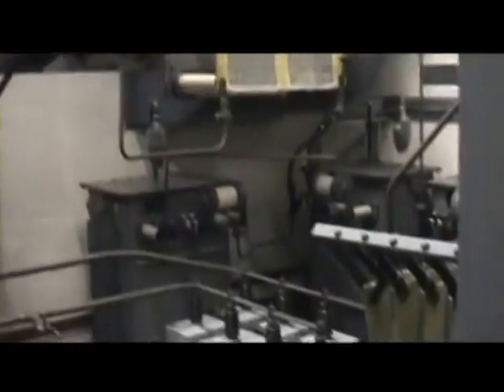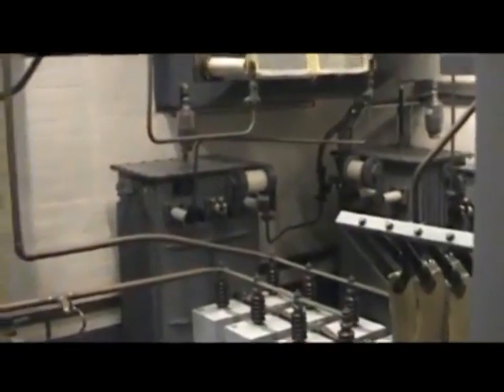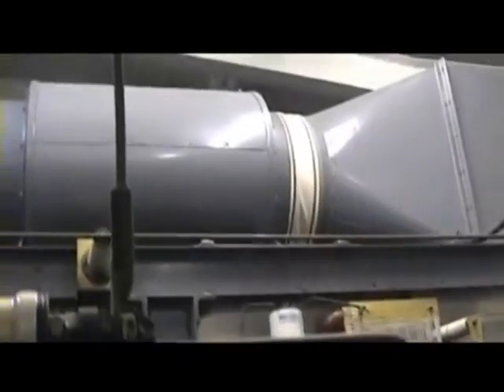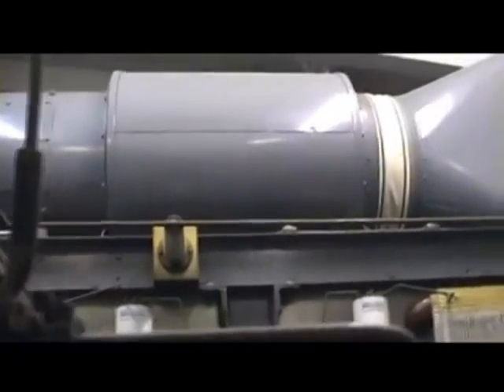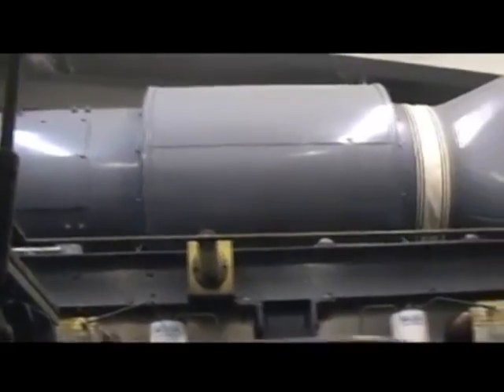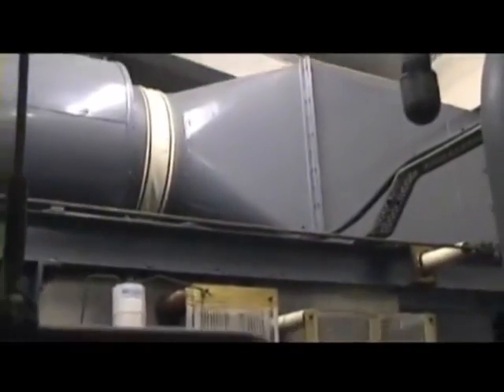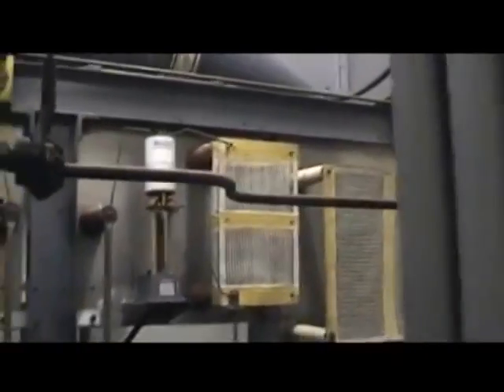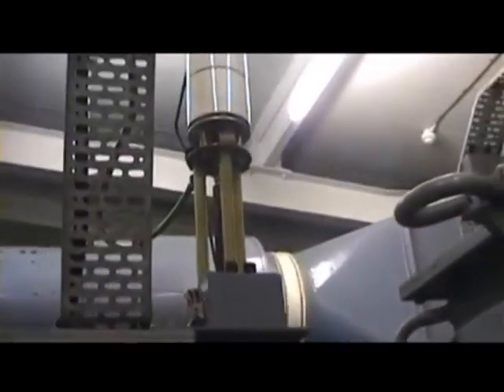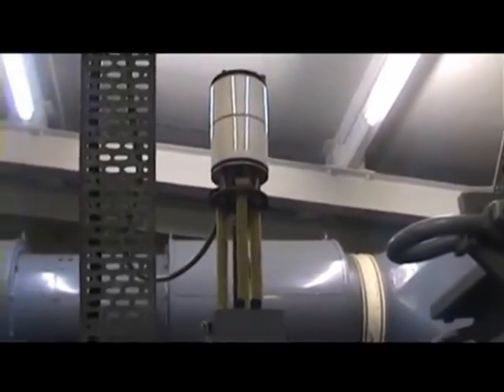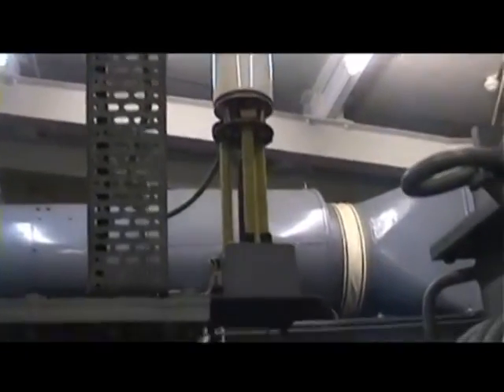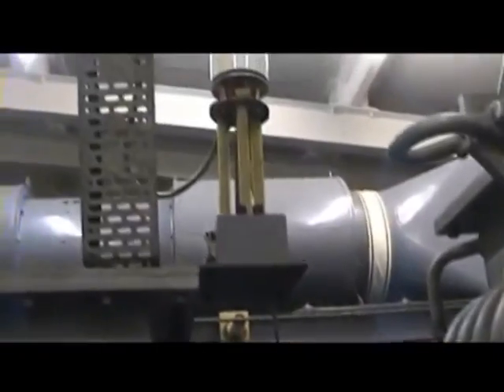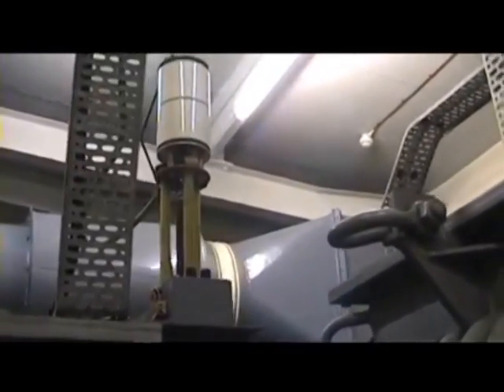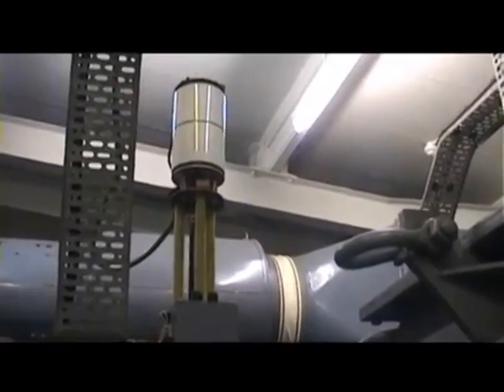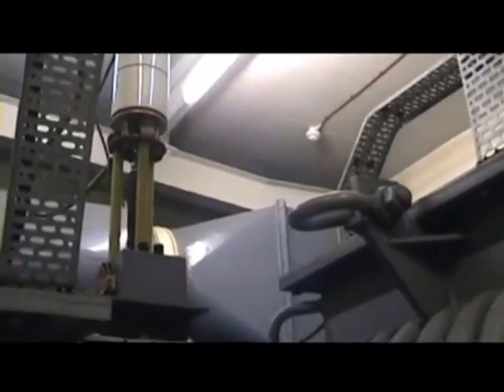There they are. Behind that and up to the high level is the air blast cooling department to generate the air that blows through the cubicles. And right above here we have one more vacuum switch with a large wire attached to it. It's got HT on one side, HV on one side, and a big fat green and yellow wire on the other. That's a crowbar switch that, when we turn the transmitter off, shorts out any HT that's left in the system. So that's the crowbar switch on the main HT. That's one you don't want to fail when it's running program.